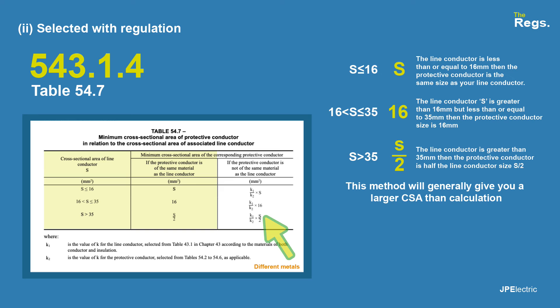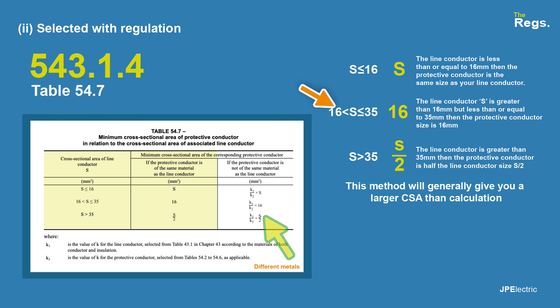The other method of selecting your protective conductor is using table 54.7. The regulation is 543.1.4, and this gives you the minimum cross-sectional area of the protective conductor in relation to the cross-sectional area of the line conductor. If the line conductor is less than or equal to 16mm², the protective conductor is the same size. If it's greater than 16mm² but less than or equal to 35mm², you use a 16mm² protective conductor. And if the line conductor is greater than 35mm², the protective conductor is half the line conductor size. This method generally gives a larger cross-sectional area than calculation, and it errs on the side of caution.